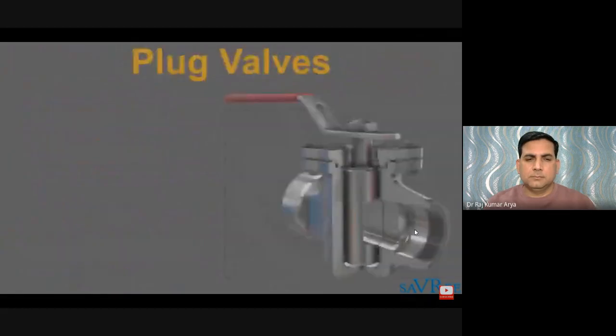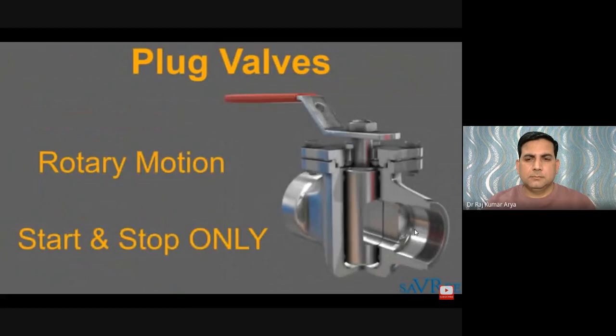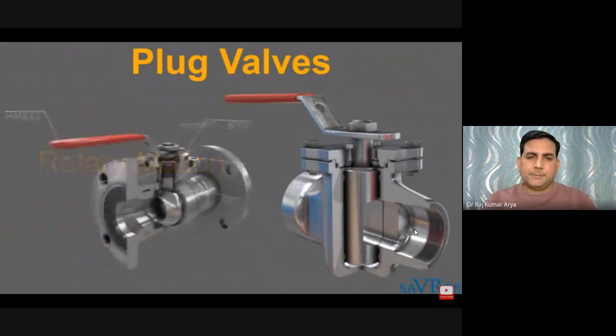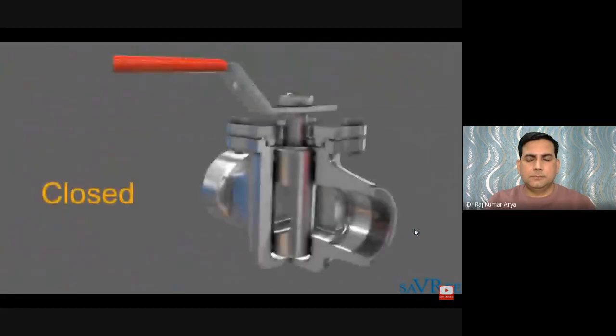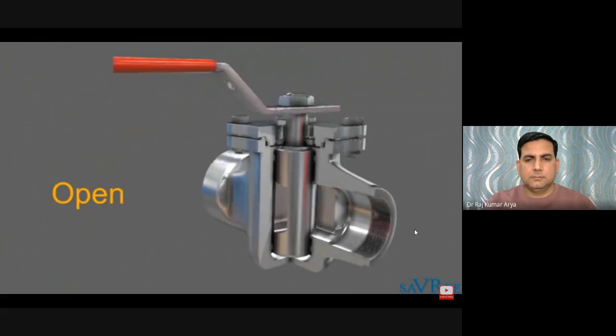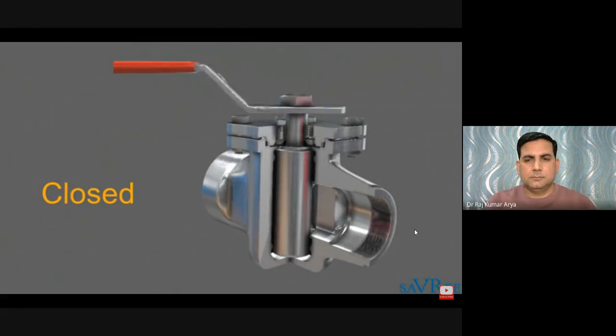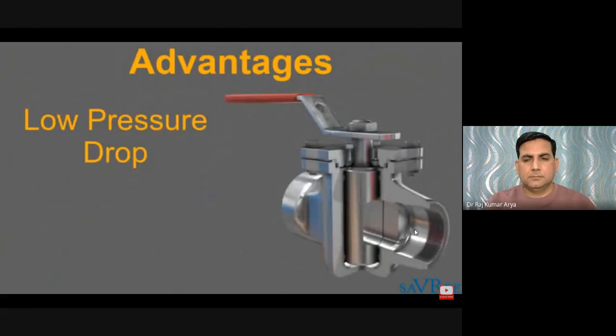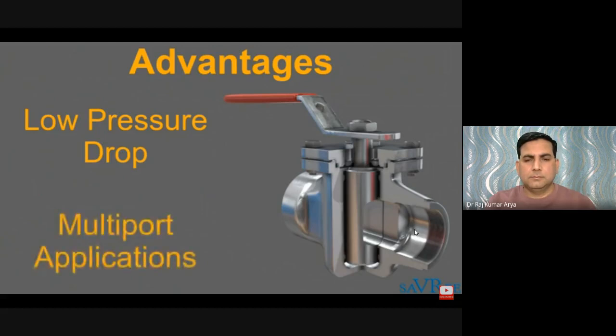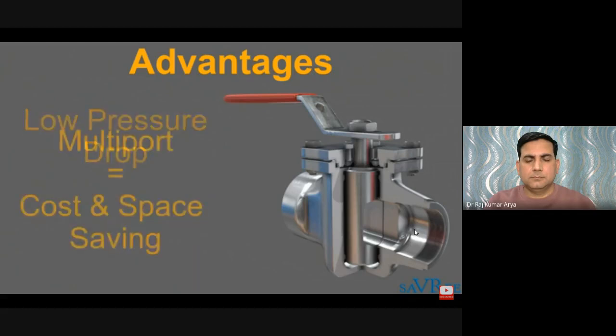A plug valve is a rotary motion valve used to start or stop flow. The name is derived from the shape of the disc, which resembles a plug. The design is very similar to a ball valve. In the open position, the passage in the plug lines up with the inlet and outlet ports. When turned 90 degrees, a solid part of the plug blocks the ports and stops flow. When fully open, pressure drop across the valve is very low. Plug valves are easy to adapt for multi-port applications, potentially eliminating the need for up to four conventional shut-off valves, making them a considerable cost and space saving.